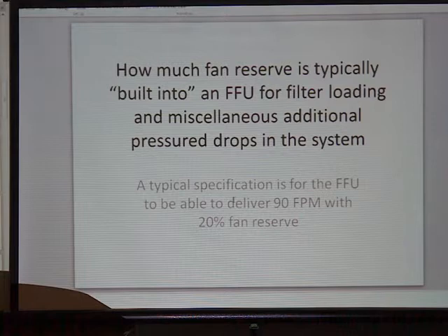And so the first thing is, when you're using an airborne molecular contamination filter in a fan filter, from the fan filter standpoint, it's a pre-filter like any other pre-filter, and it represents a pressure drop to the system that was not there before you put the pre-filter on. Typically fan filters are specified with about 20% reserve for filter loading, but not much more than that because customers typically don't want to pay for a lot more fan than they're going to use.